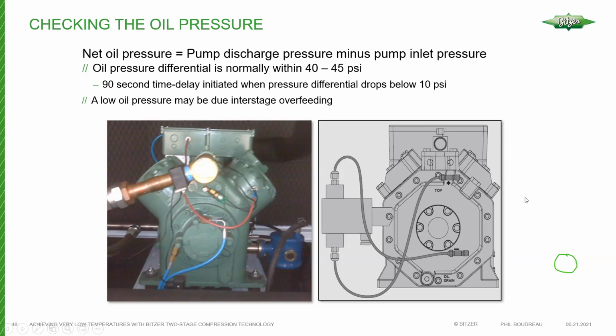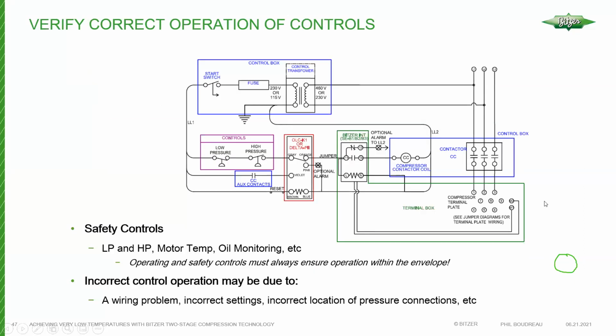So, and I'll skip this slide here. This is just on checking oil pressure. Always check between the pump, negative and positive, or I guess you could check the crankcase versus the positive, but never check oil pressure based on suction pressure.